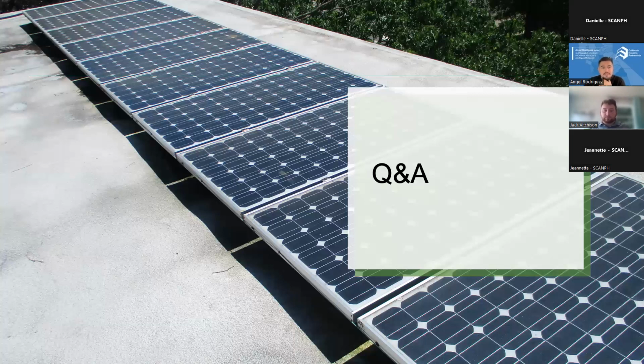Next question we have is, does crossover impact gas-fired boilers and heat pump boilers equally, or do heat pump boilers suffer more? That's a great question. Unfortunately, heat pump water heaters suffer more, because gas has really high recovery, so it can overcome that load being inflated due to crossover. Not to say that heat pumps can't meet that load. Sometimes they can, sometimes they can't. However, your heat pump is going to operate more frequently, and you're going to see an increase in utilities. Even though you may see a slight increase in gas, you're going to see a bigger impact for heat pump water heaters.